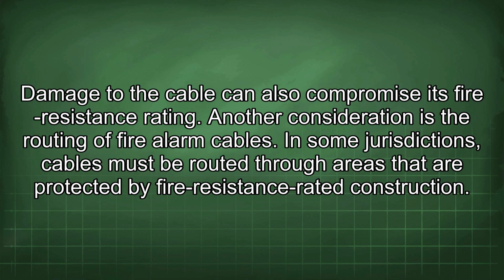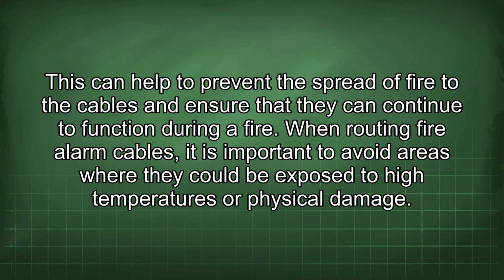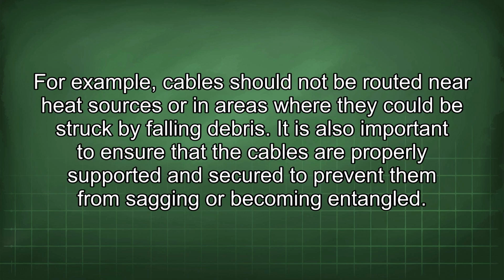Another consideration is the routing of fire alarm cables. In some jurisdictions, cables must be routed through areas that are protected by fire resistance rated construction. This can help to prevent the spread of fire to the cables and ensure that they can continue to function during a fire. When routing fire alarm cables, it is important to avoid areas where they could be exposed to high temperatures or physical damage. For example, cables should not be routed near heat sources or in areas where they could be struck by falling debris. It is also important to ensure that the cables are properly supported and secured to prevent them from sagging or becoming entangled.